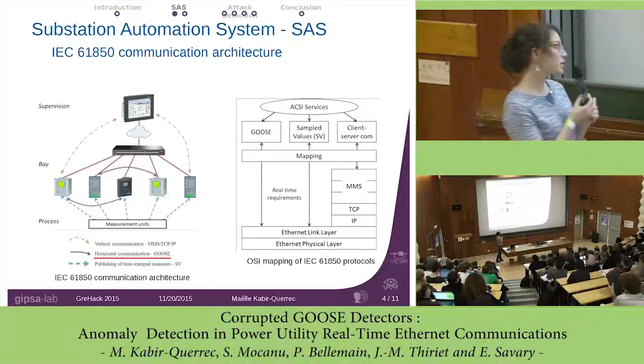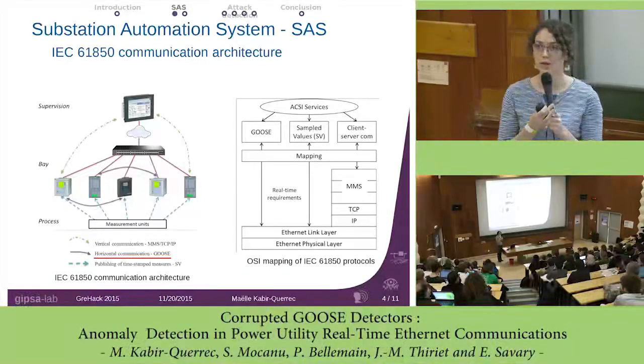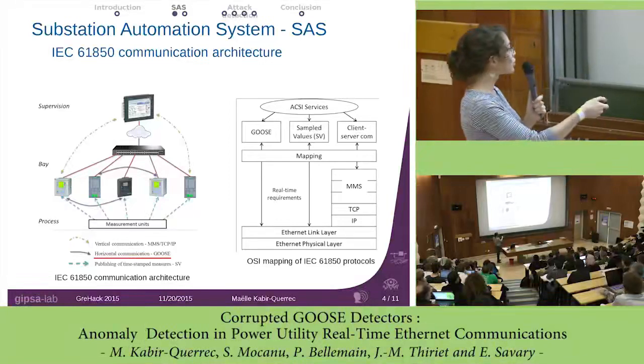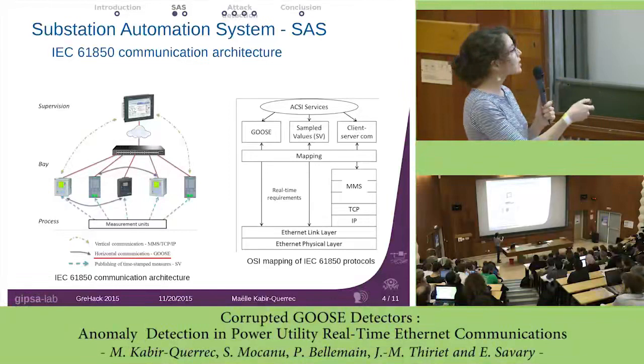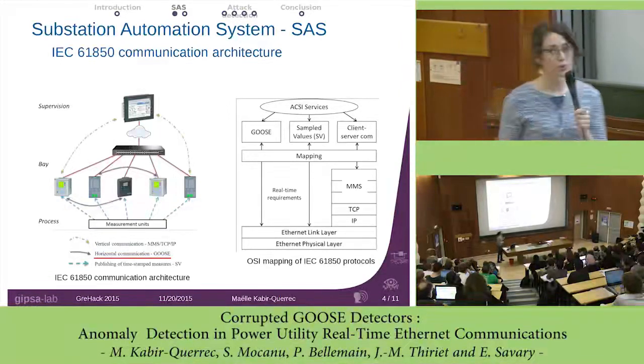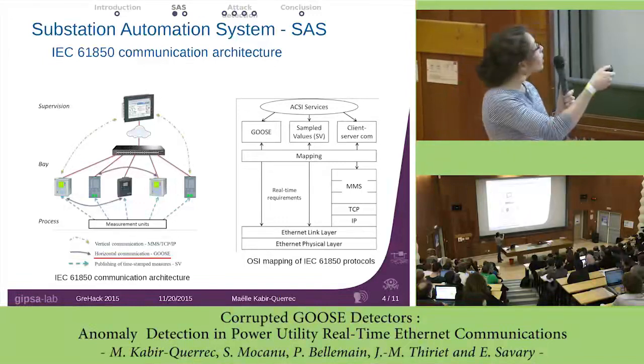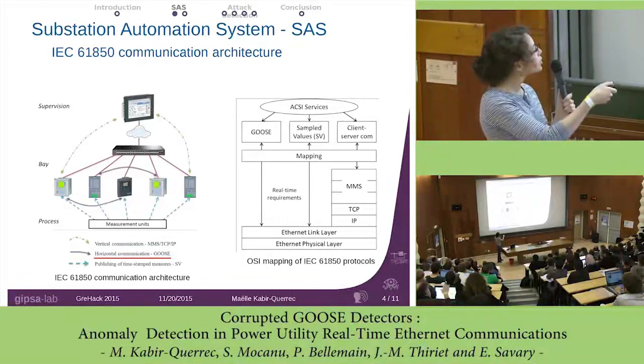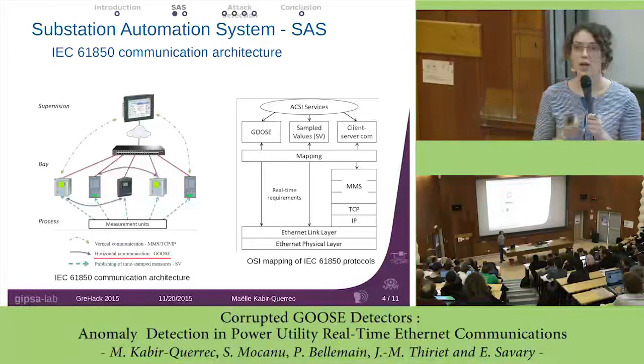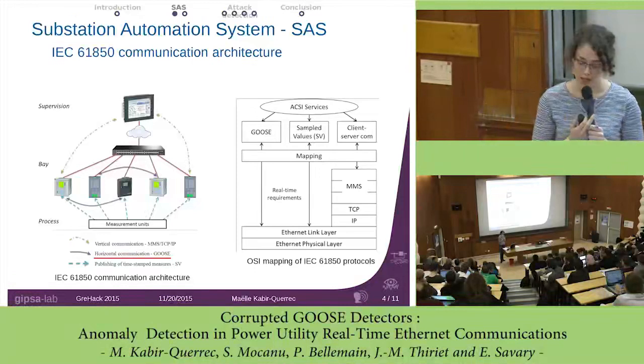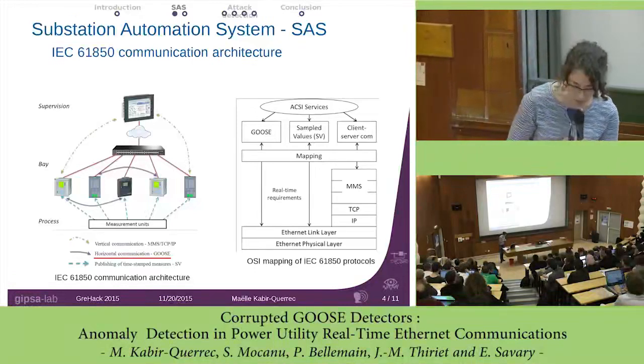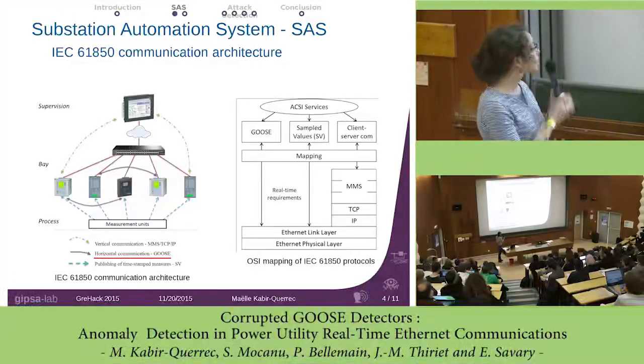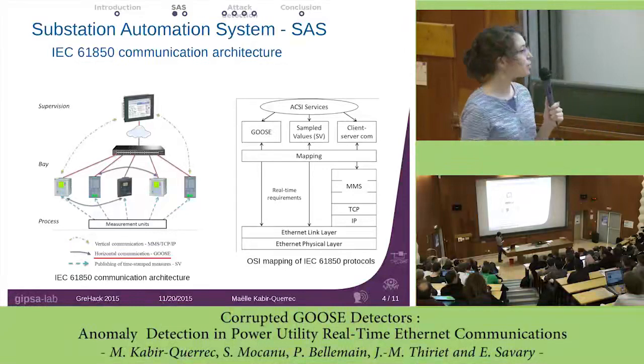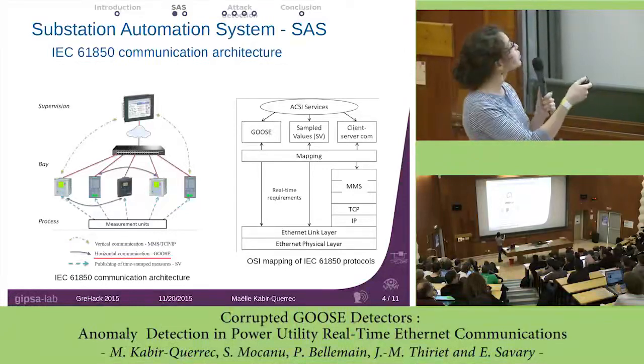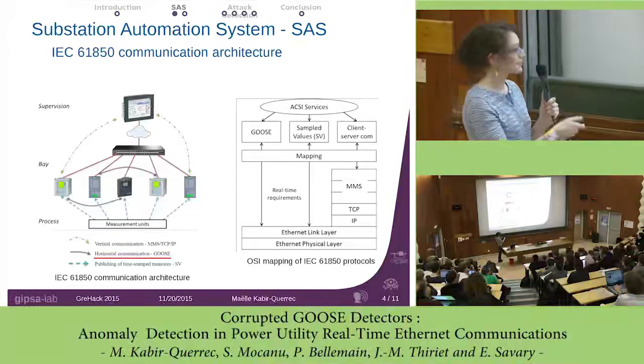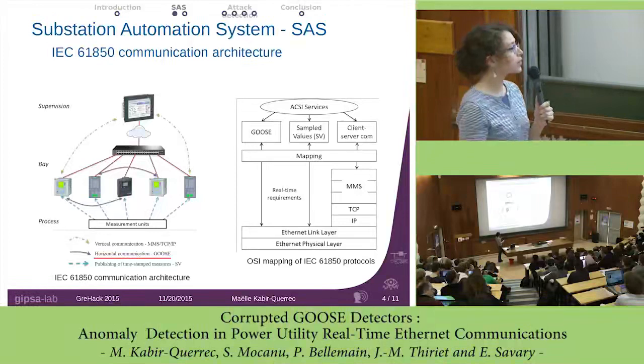There are 3 protocols involved according to the units exchanging information. Measurement units send their measurements to the IED through the Sampled Values protocol. The IEDs communicate with each other using the GOOSE protocol, which is the one I will talk about more deeply today. GOOSE means Generic Object-Oriented Substation Event. The last protocol, MMS, Manufacturing Message Specification, is for the communication between supervision and the actuators. All those protocols are based on Ethernet.